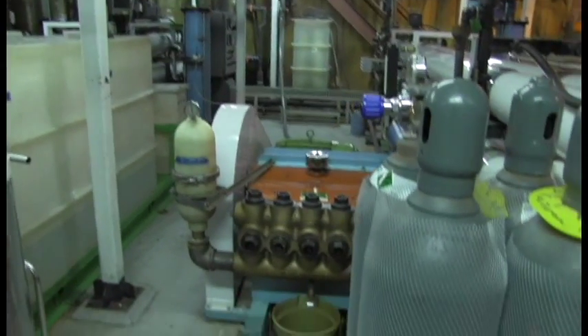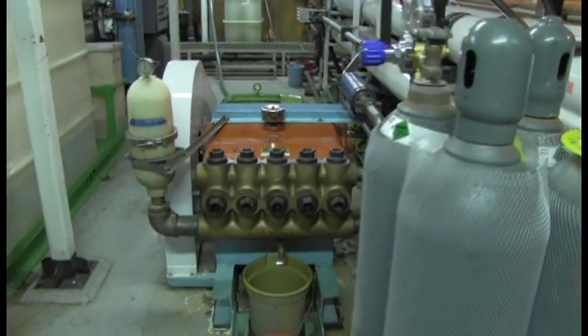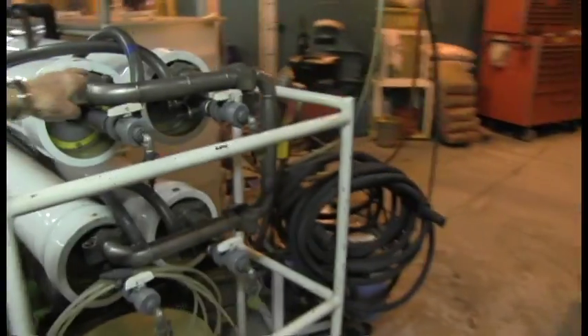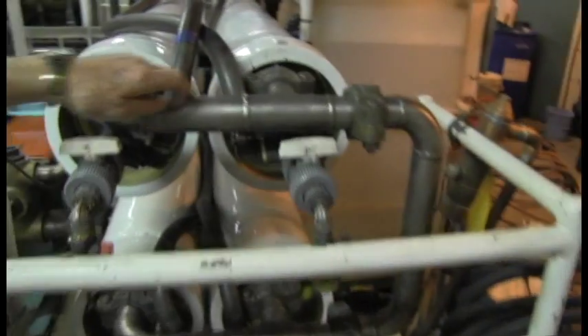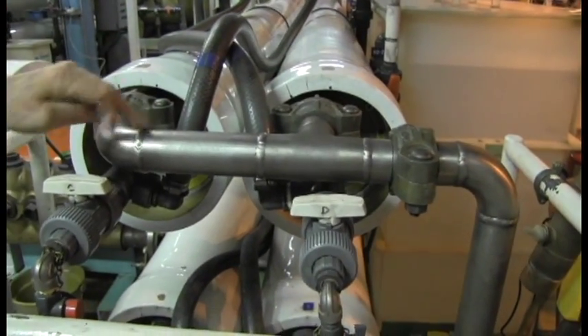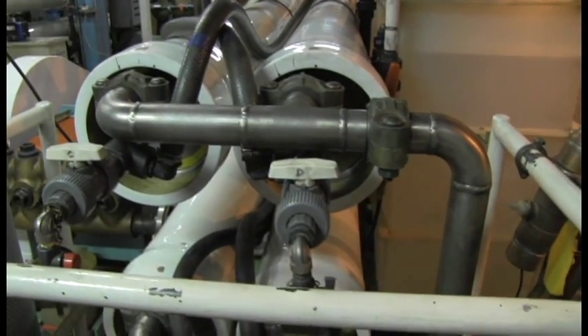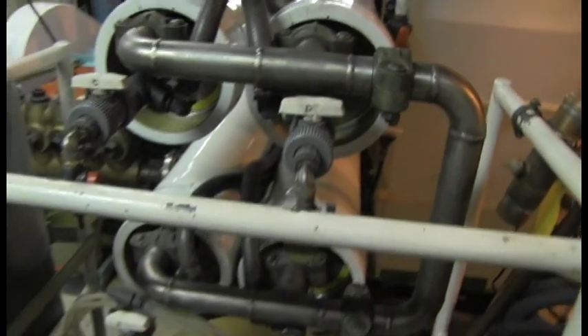We jack the pressure up to over 800 pounds per square inch, and this is what this pump does. This is a high-pressure pump — I mean really high pressure, 800 pounds. Notice the piping here is all stainless steel with certified welded joints. You do not want these things to blow apart. 800 pounds is a lot of pressure.